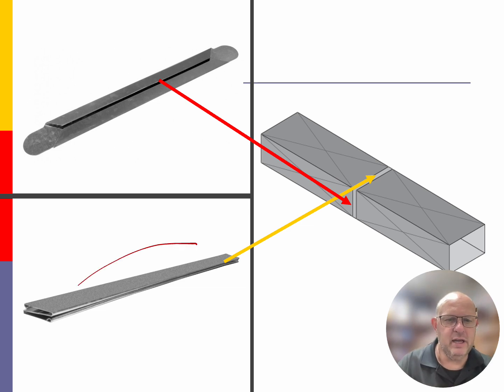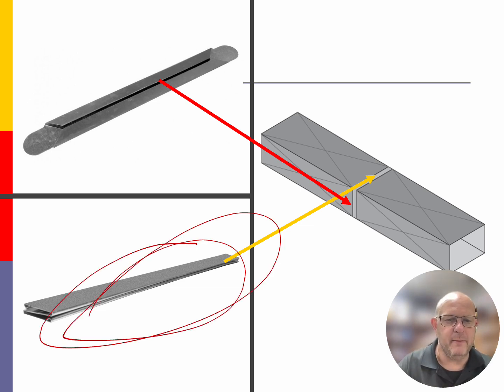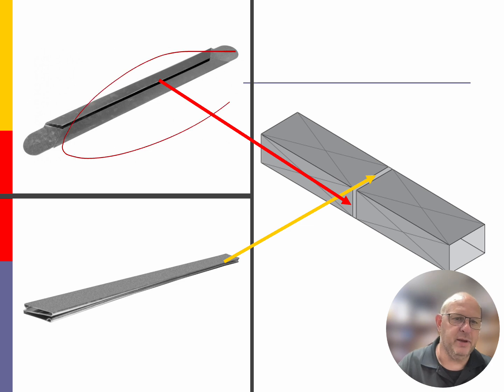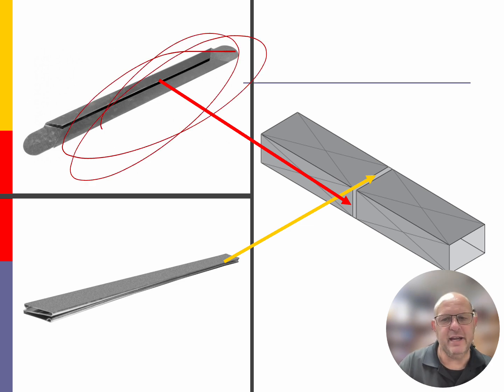So once again, here's your S-lock, okay, and then once again up here, here's your drive cleat. After we get done putting our drive cleats on the shorter side of the ductwork, we will bend those little tabs over the ductwork itself. Now, the purpose of bending those little tabs over the ductwork is so that we are securing that ductwork in place.